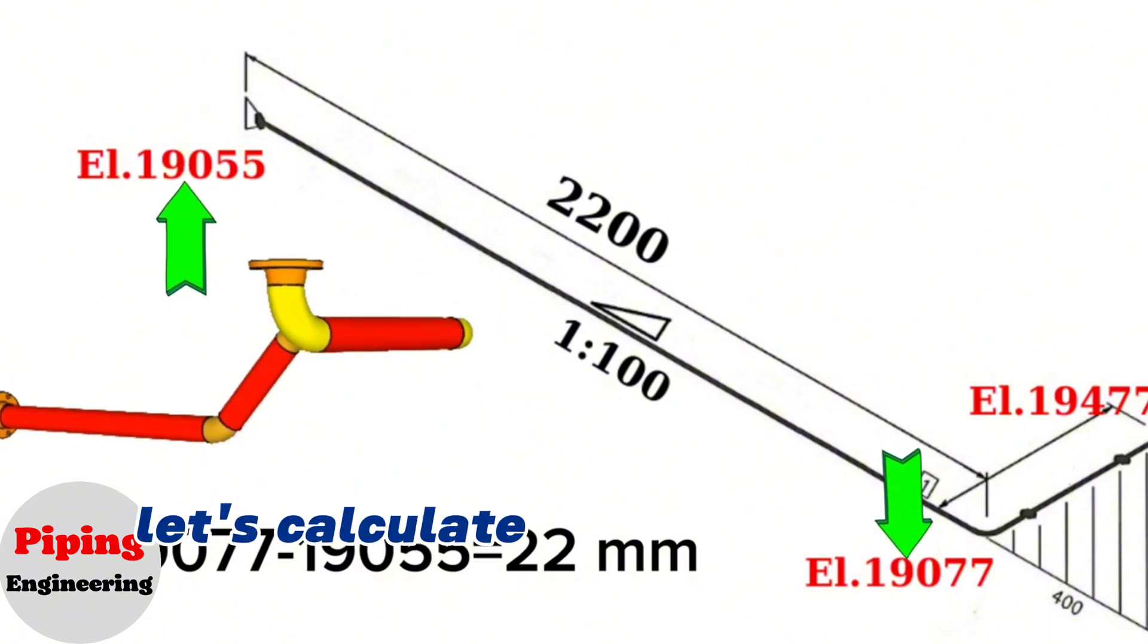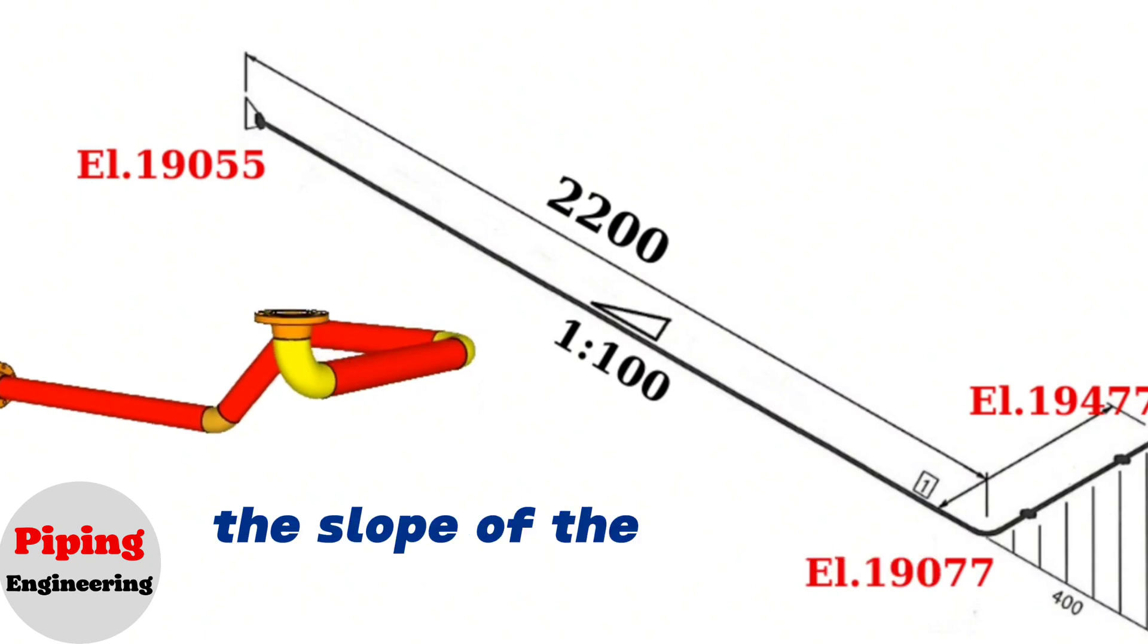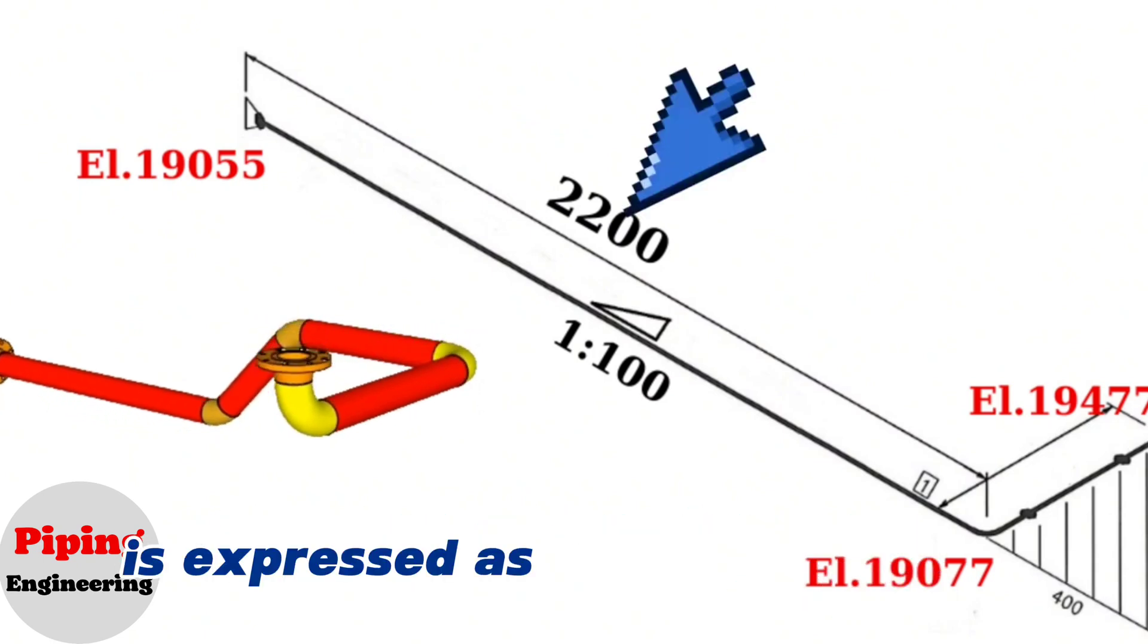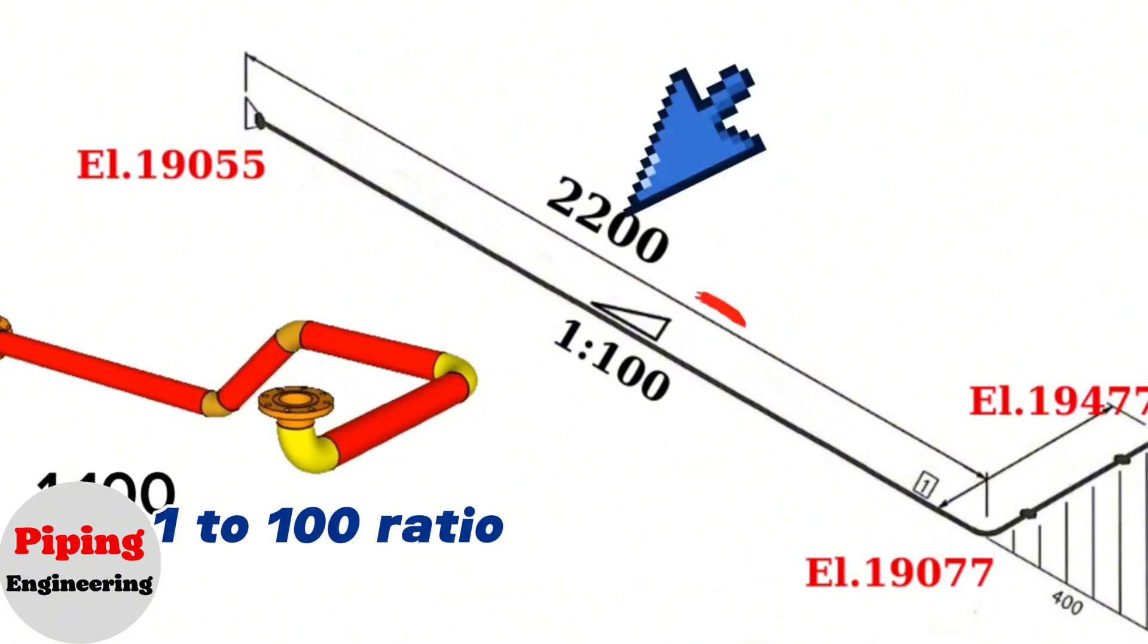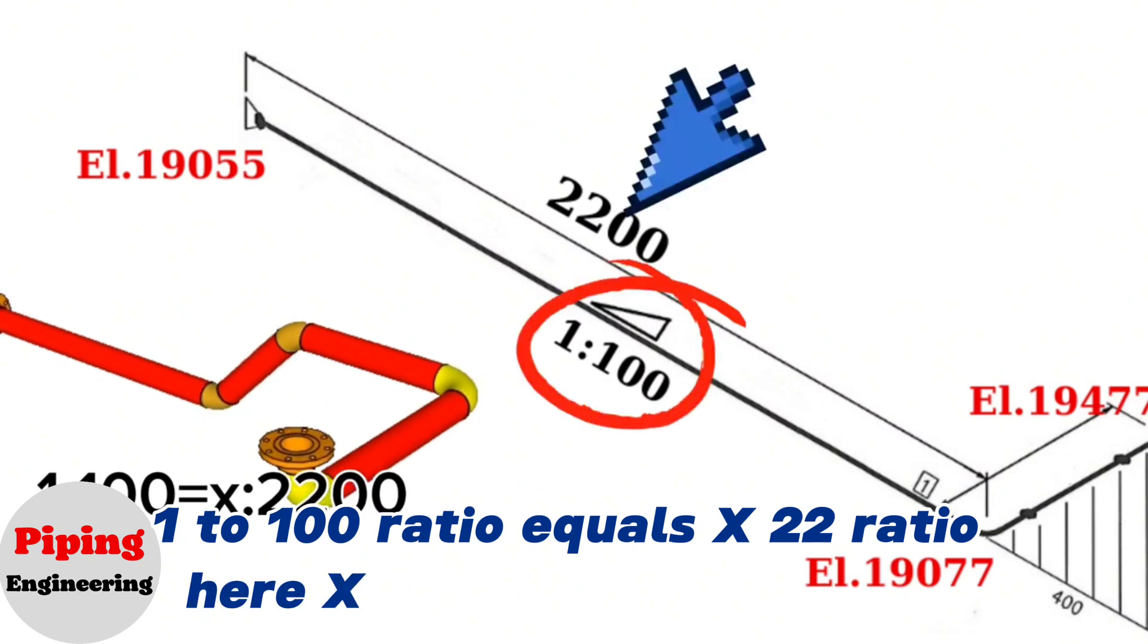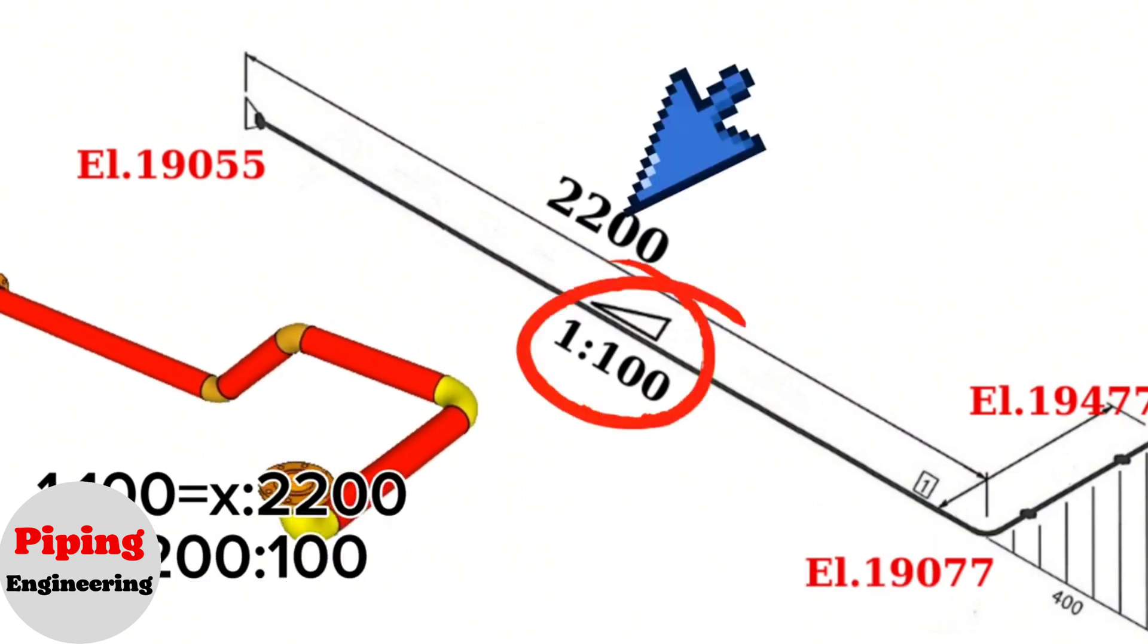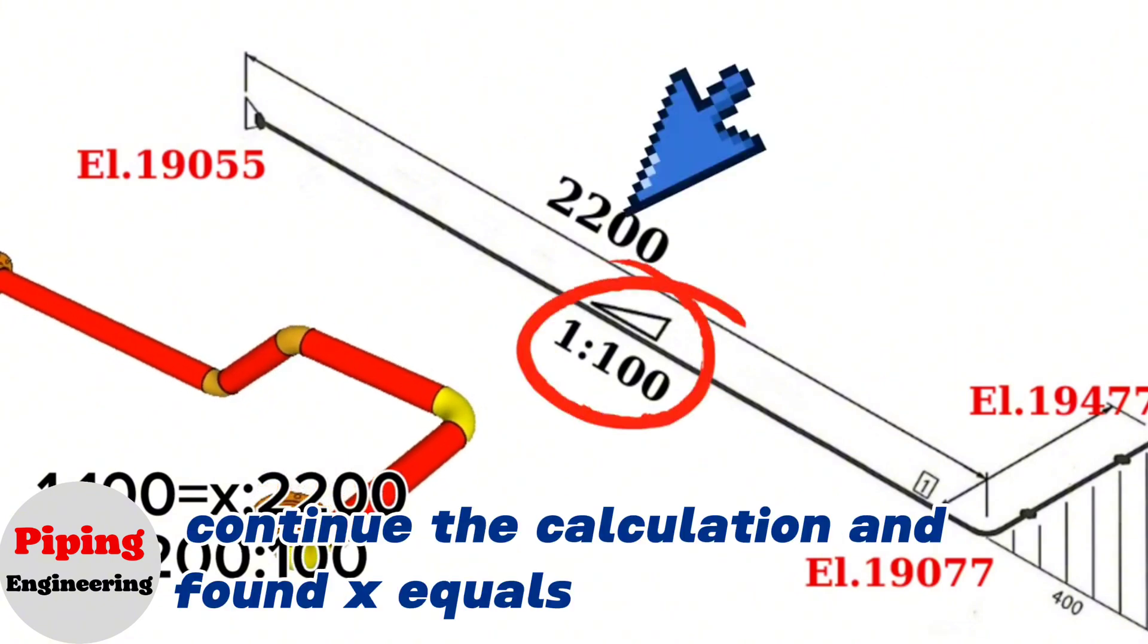Let's calculate with slope ratio now. In this pipe isometric drawing, the slope at a horizontal distance of 2200 is expressed as a ratio of 1 to 100. 1 to 100 ratio equals x to 2200 ratio. Here x equals 2200 to 100 ratio. Continue the calculation and found x equals 22 mm.